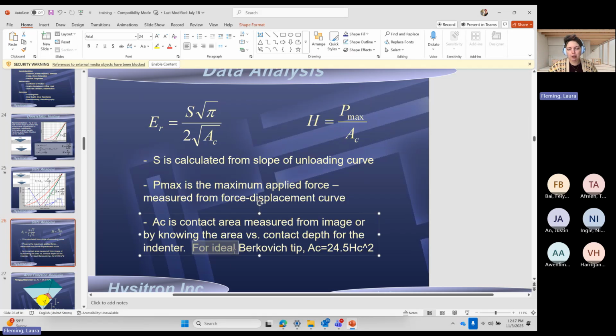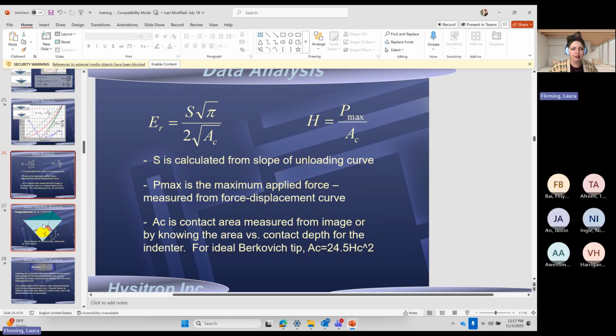For an ideal Berkovich probe, so Berkovich is kind of the default tip for nanoindentation, the rule of thumb is if you can use a Berkovich, you should. It's a very specific three-sided pyramid with a very specific angle. If we went back to 8th grade geometry, I'm sure we could figure out how to do that calculation. You go down the pyramid and you cut it and you look at how far down you went versus what the area is, and you can make a relationship. For an ideal Berkovich, that contact area is 24.5 HC squared.